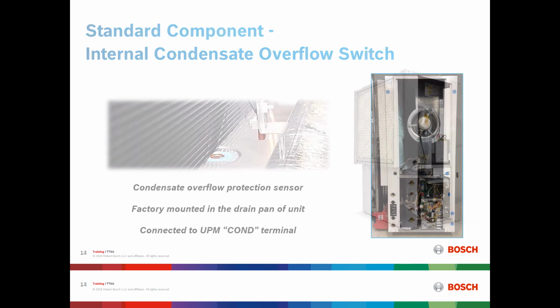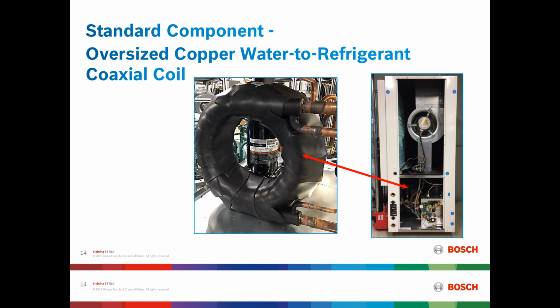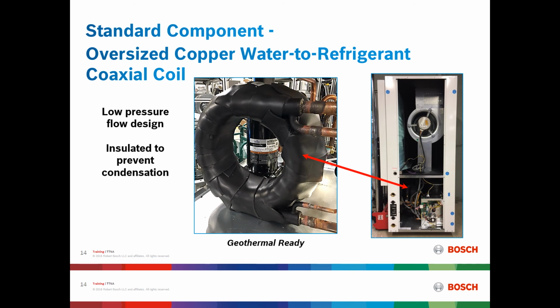Inside this pan will be an internal condensate overflow switch. The sensor will detect water backing up inside the pan. It is connected to the unit protection module, or control board, to the condensate terminal and will alert the unit to stop the compressor if the water backs up and touches the switch. All SM-REV-Vs, as standard, will have an oversized copper water-to-refrigerant coaxial coil. This coil will be wrapped with insulation. It has a low-pressure flow design, and it is insulated to prevent condensation. We commonly refer to this wrapping as making the unit geothermal ready.